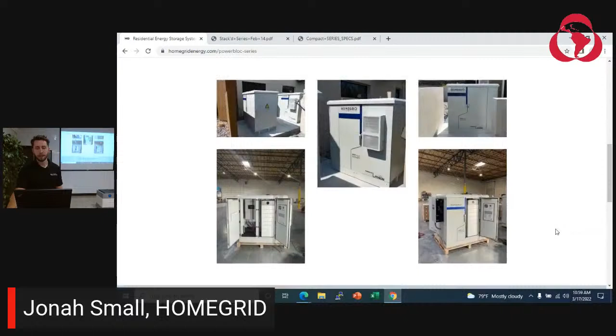The last one I'll run through for HOMEGRID is our Power Block series, which we've also recently upgraded. It's a similar model: a large commercial cabinet that is weatherproof and temperature controlled with air conditioning and heating, and it comes pre-installed with batteries and solars on it. We can fit up to 4 full stacks of these batteries in this cabinet, and up to 3 solars on the outside—1, 2, or 3—with 1 to 4 stacks inside, giving a capacity range inside one cabinet of 9.6 to 153 kilowatt hours.